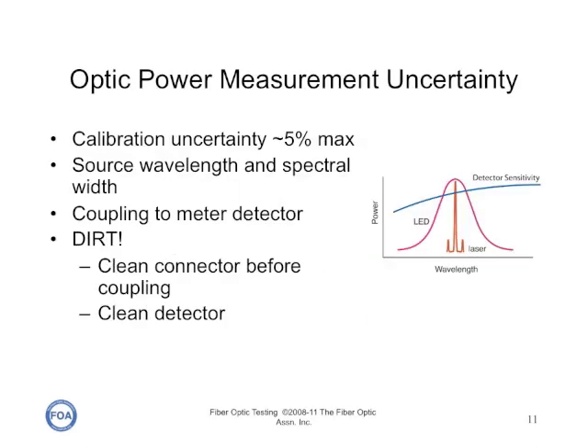The uncertainty of an optical power meter measurement depends on the calibration, the source wavelength and spectral width, the coupling to the meter, and dirt — because it's very important to clean the connectors before coupling to the meter. It's also important to occasionally clean the detector in the power meter itself.